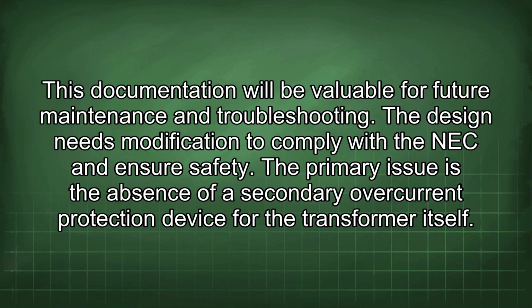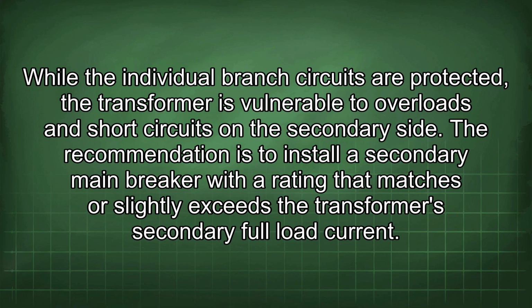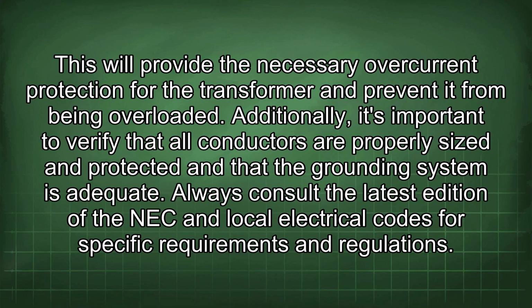The design needs modification to comply with the NEC and ensure safety. The primary issue is the absence of a secondary overcurrent protection device for the transformer itself. While the individual branch circuits are protected, the transformer is vulnerable to overloads and short circuits on the secondary side. The recommendation is to install a secondary main breaker with a rating that matches or slightly exceeds the transformer's secondary full load current. This will provide the necessary overcurrent protection for the transformer and prevent it from being overloaded.